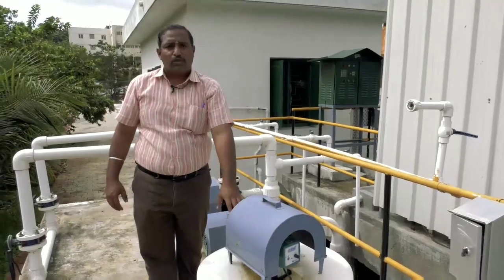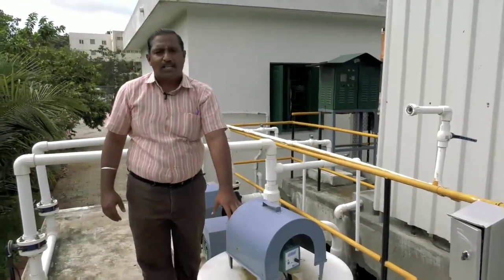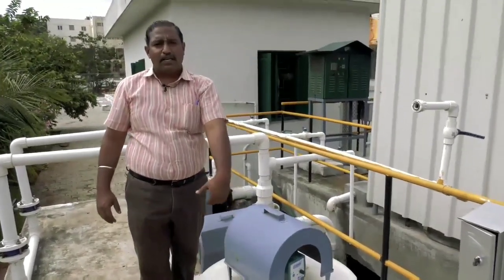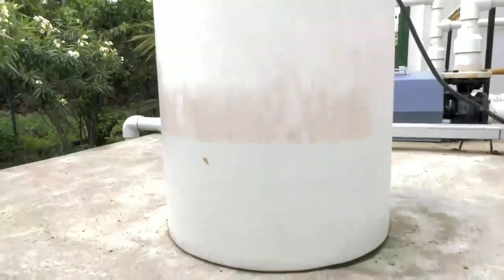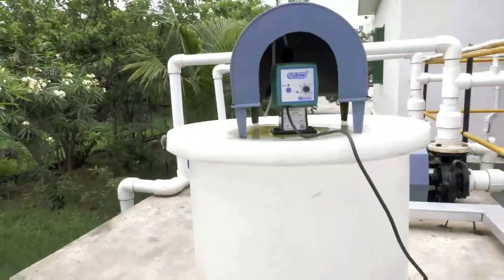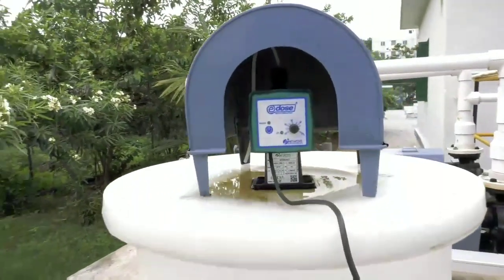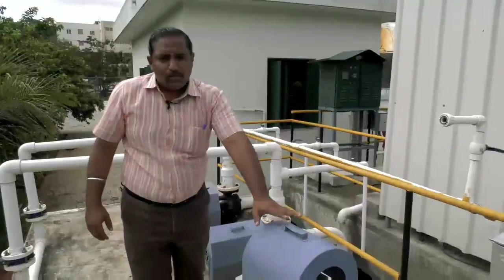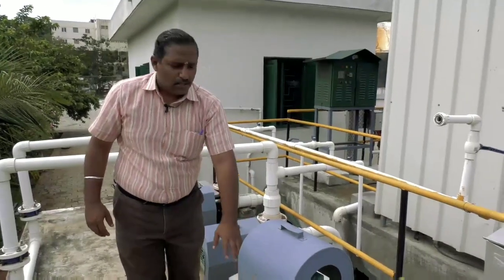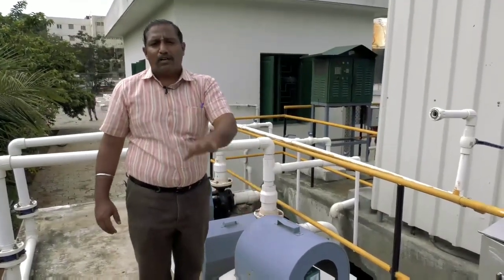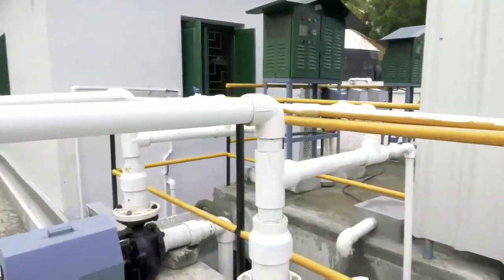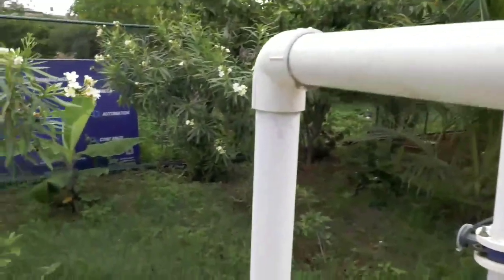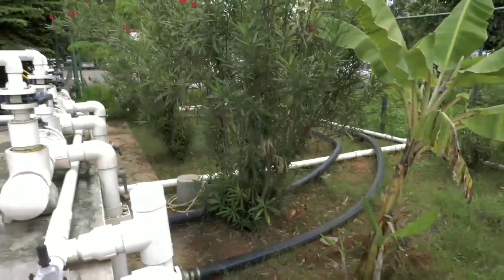Chemical disinfection is also present over here, by which I am dosing chlorine, nothing but liquid chlorine in the form of hypo, right, hypochlorous acid. So that is diluted, made into an optimum concentration, and is fed into the outlet water, right? So chemical disinfection is also present. Not only hypo I am giving, I am also giving TCCA, that is trichloroisocyanuric acid. So that also I am giving in this chemical dosing process, whereby the pathogenic microorganisms are killed.